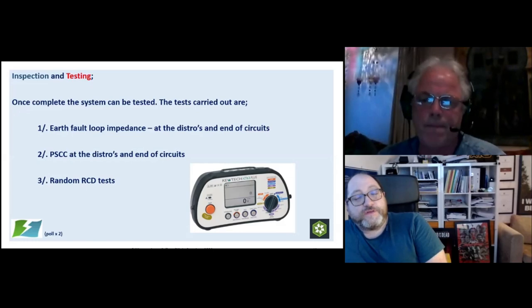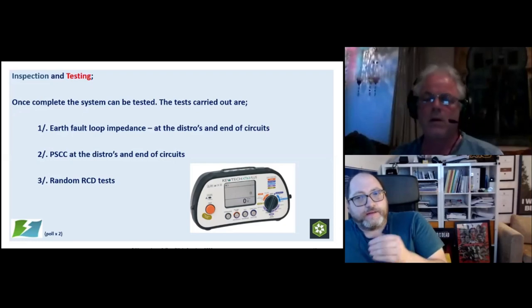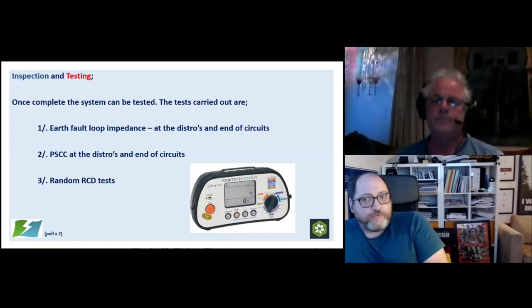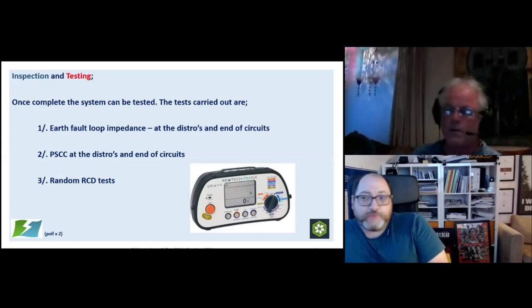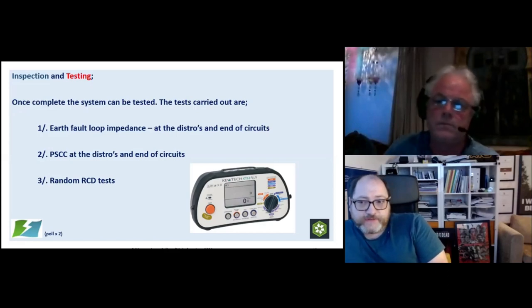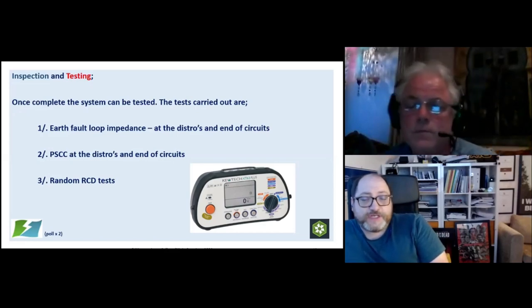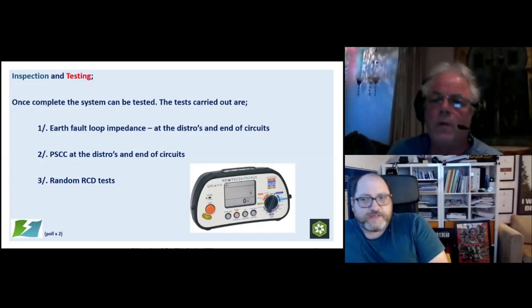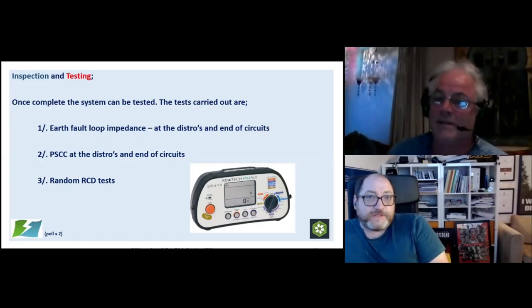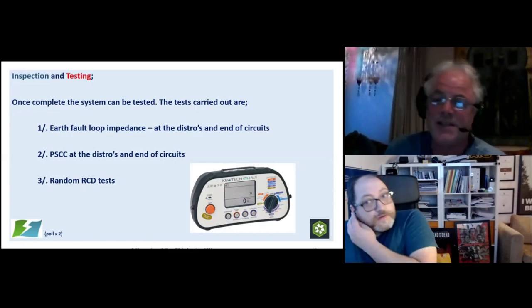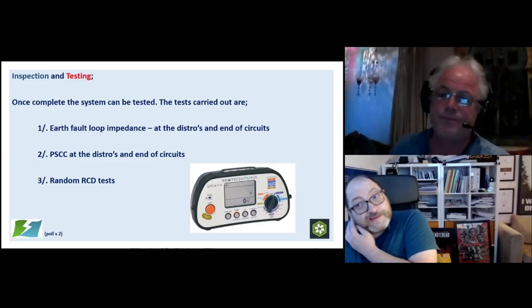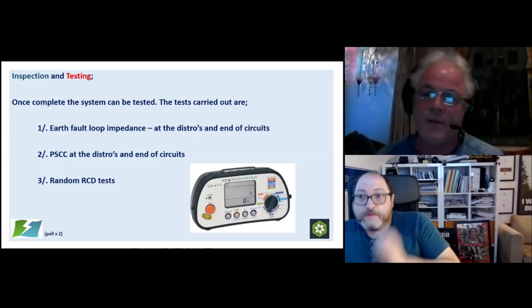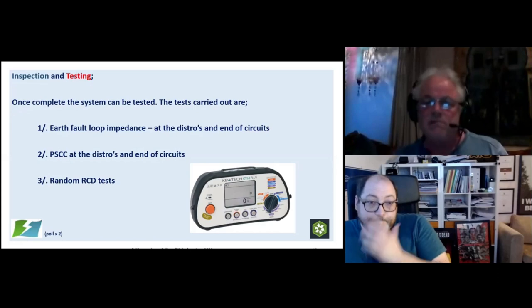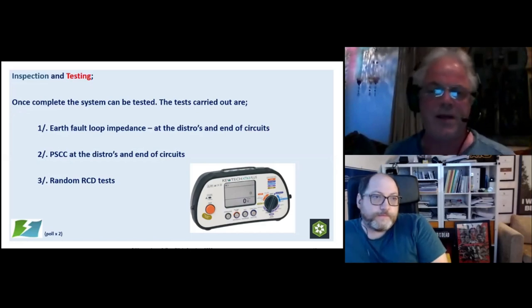It's important to note that you said should. We have, in our experience, seen some companies testing, like PAT testing distros, and not really having the right instrument to properly test RCD effectiveness. No. More just continuity and insulation testing. So it is very important that you verify RCDs yourself. I've seen a company testing a distro who didn't know what an RCD test was. Yeah, exactly. They were a PAT testing firm and didn't know what an RCD test was. Okay, I don't think you should be doing that, guys.